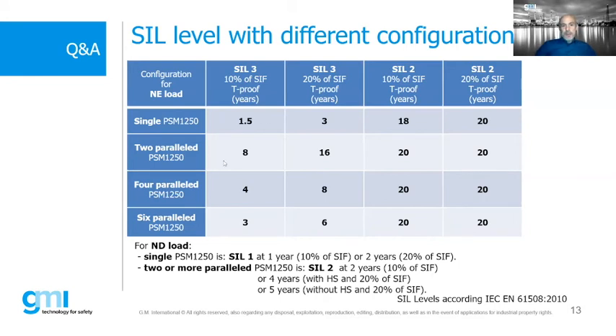If I use the same power supplies in two in parallel, so in redundant, I see that I increase my proof test time a lot. I reduce my testing or maintenance on my system to 8 and 16 years. And that is a valid procedure. For 4 or 6 parallel power supplies, I have different values. Besides, there are also the values for normal de-energized load, which are a little bit different.